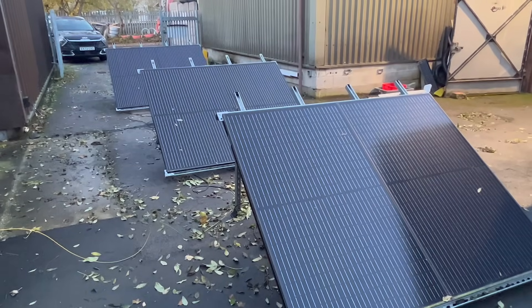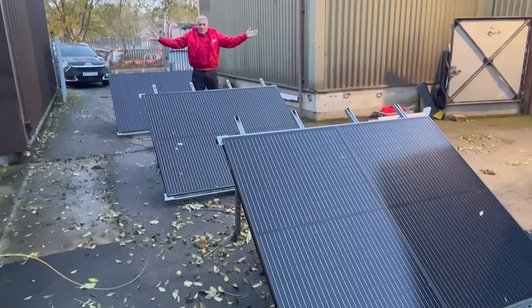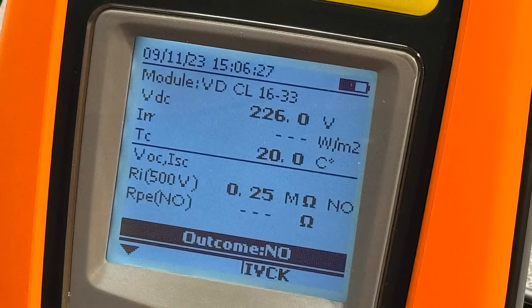In a previous video on solar PV installation, we ended up with a problem. The PV string insulation test results in our small installation here at Lineside Studios were inconsistent, to say the least. In certain test cycles, the insulation readings fell below the required 1 megaohm pass limit specified in the IEC and BS standards, resulting in a test failure.